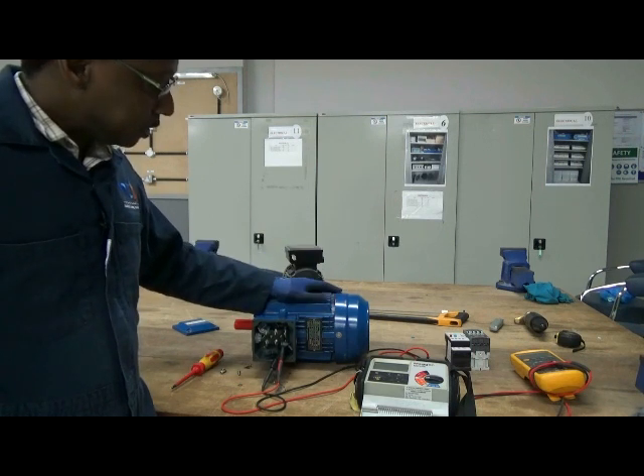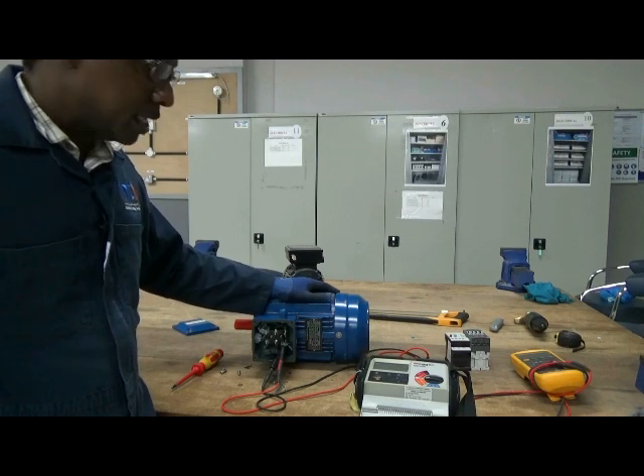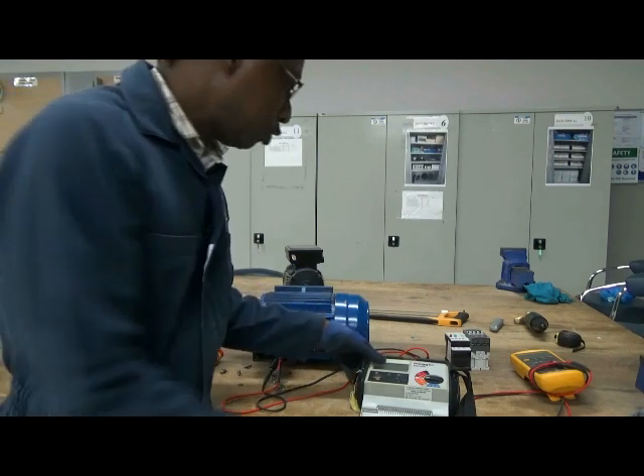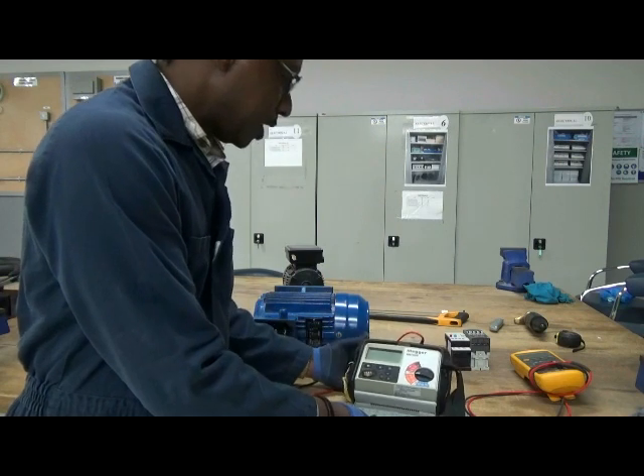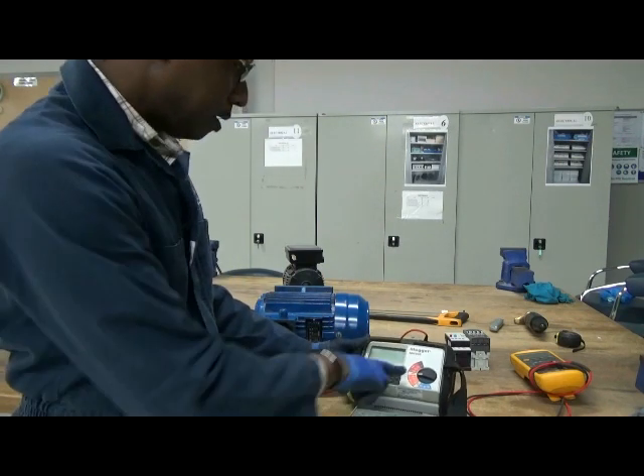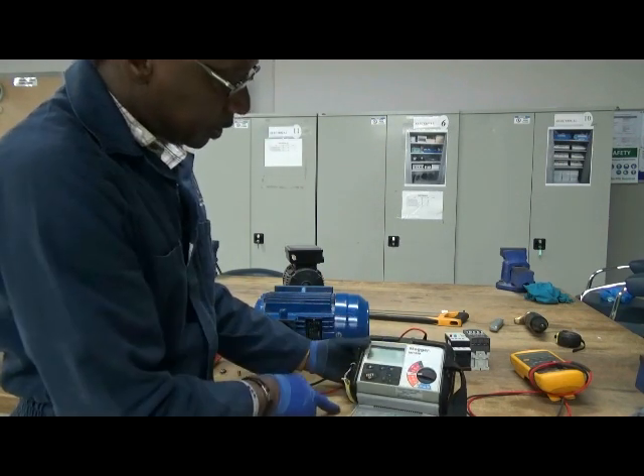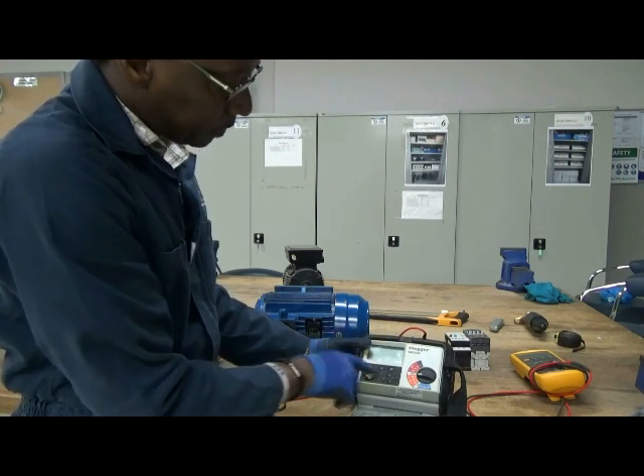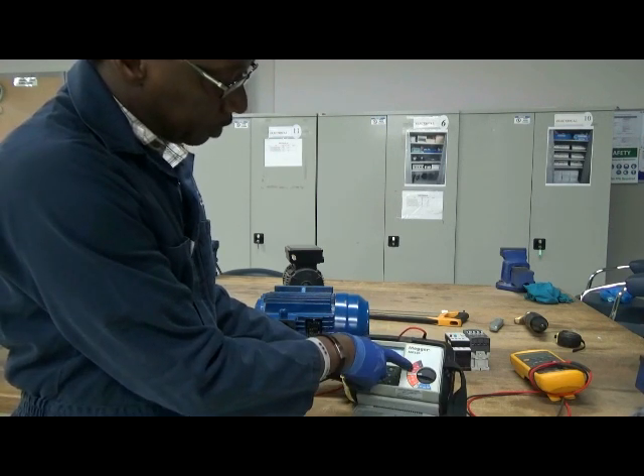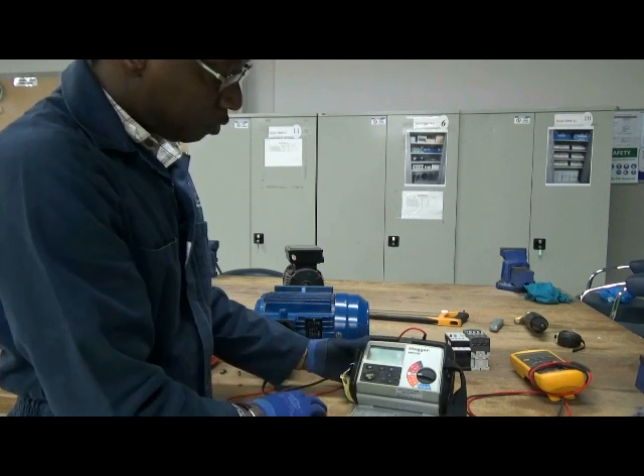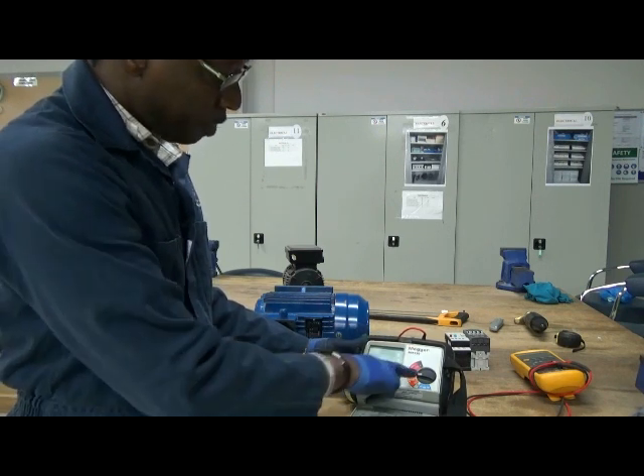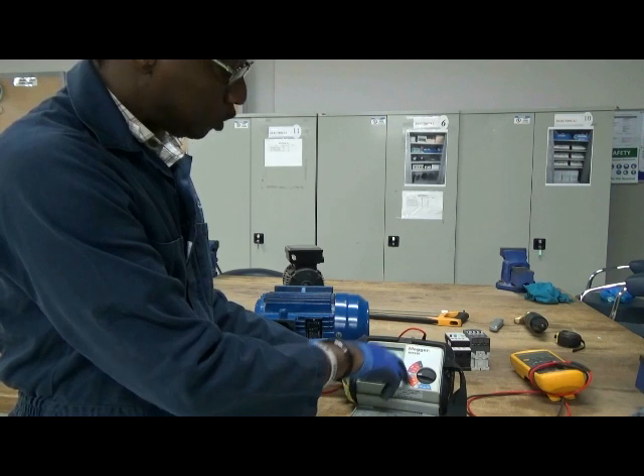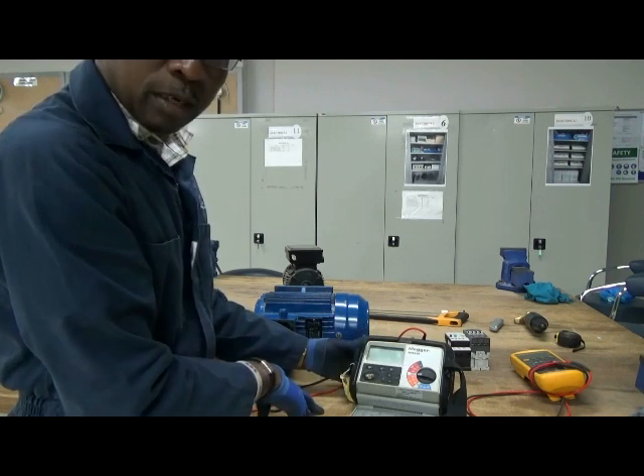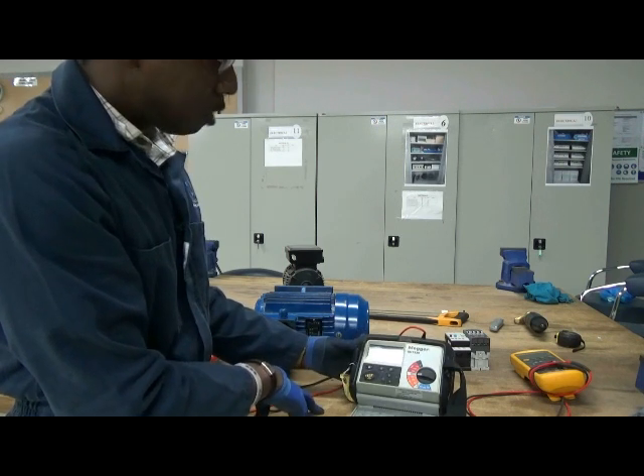So this operates at 380, and twice as much would be about 600. But this kind of instrument I've got, you can see here, the voltage range is in red. It starts from 250, 500 volts, and 1 kilo. 1 kilo means 1,000 volts. So 500 is not twice 380, so I'll go up to about 1 kV, which is 1,000 volts.